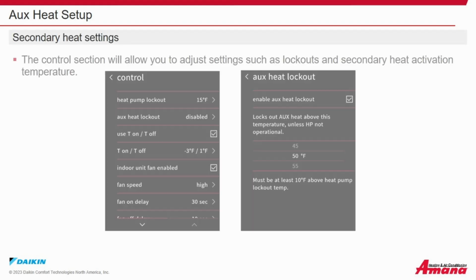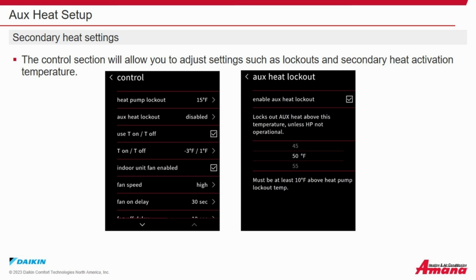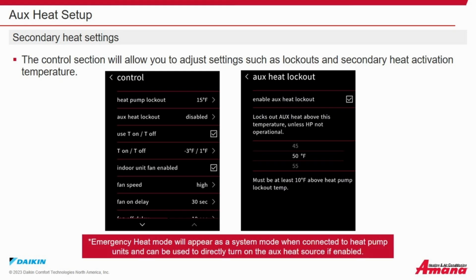Auxiliary heat setup. Secondary heat settings. The control will allow you to adjust settings such as lockout and secondary heat activation temperature. Emergency heat mode will appear as a system mode when connected to heat pump units and can be used to directly turn on auxiliary heat source if enabled.